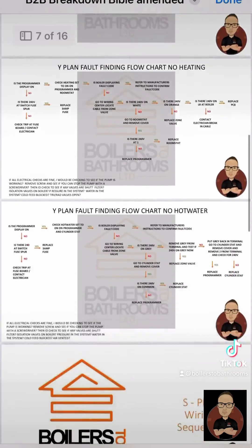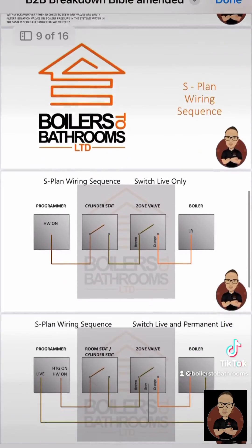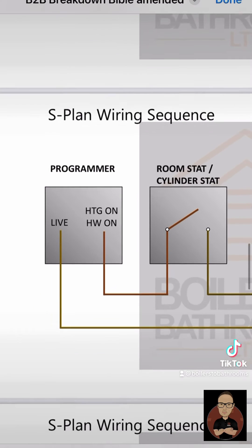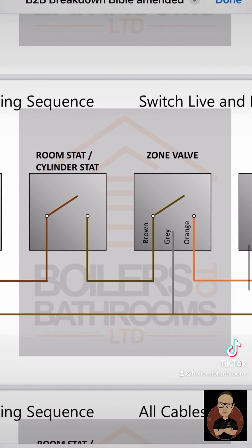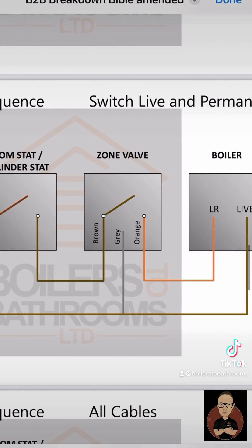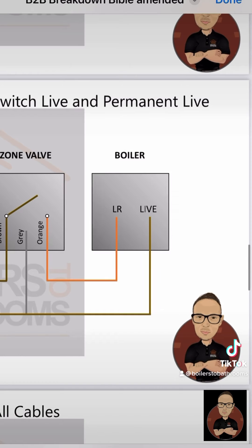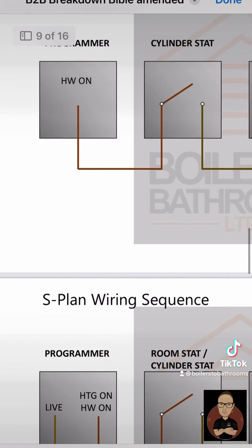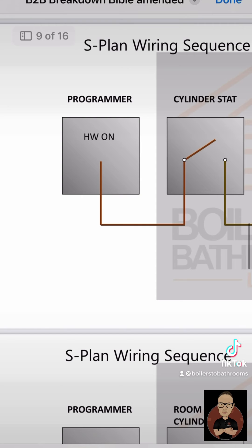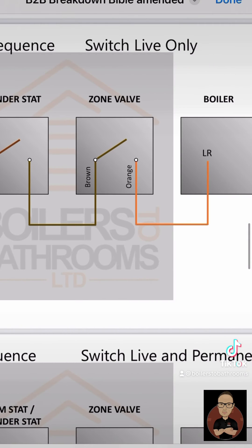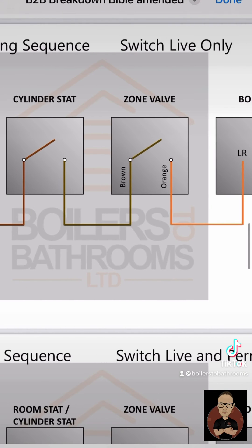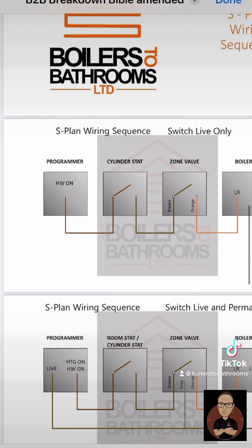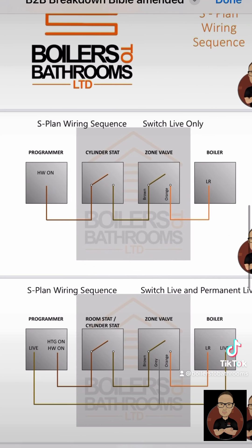I haven't done the S-plan with a combi system yet but it's technically the same thing. If you've got a programmable room stat, the programmer and the room stat blend into one. You've got your brown coming up to your zone valve, which then goes through to feed your boiler. In this instance we weren't getting 240 on the zone valve on brown, so we know it's the room stat. I will be doing a proper one for combi in two zones.